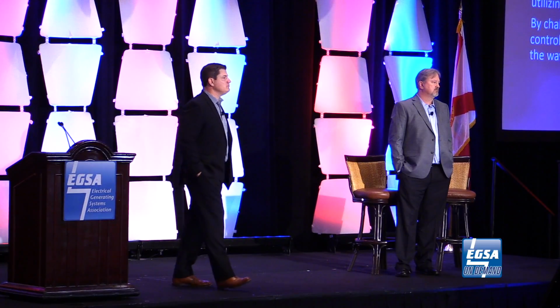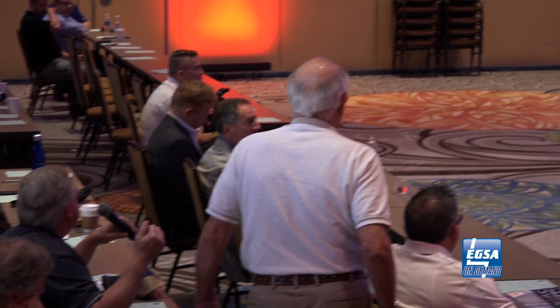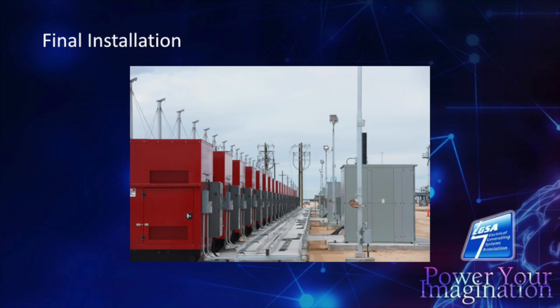So I didn't see any transformers. So you're generating at 480 and then stepping up? No, we step up to 1247. I think if I can go back to way back, not too far back. Right there. Here we go. So each group, each segmented bus has its own 2500 kVA transformer, and then arc flash calculations decided that we were going to have these group breakers, which we ended up needing to energize those transformers.